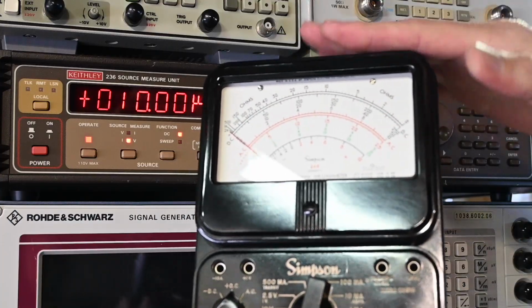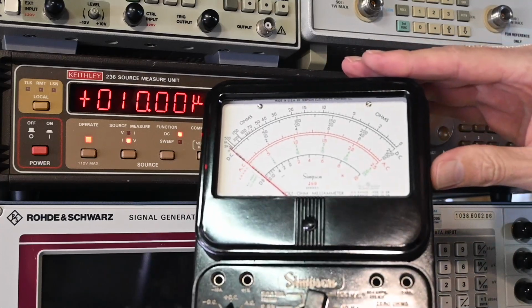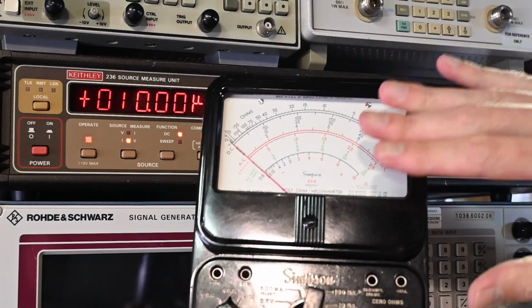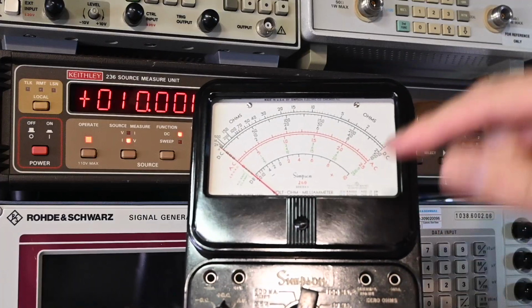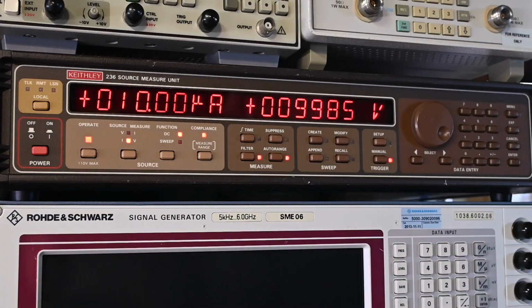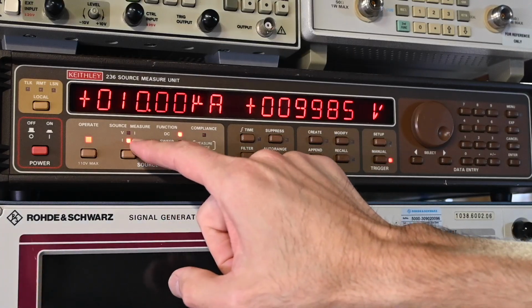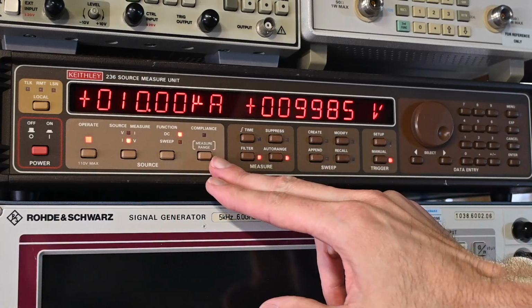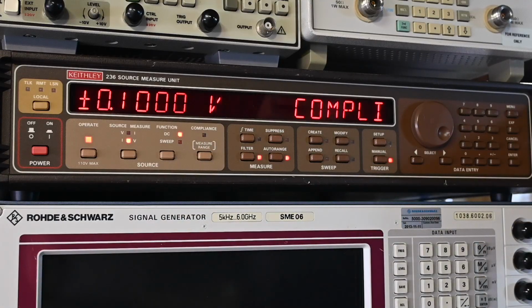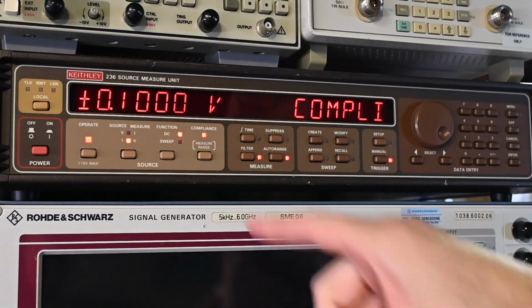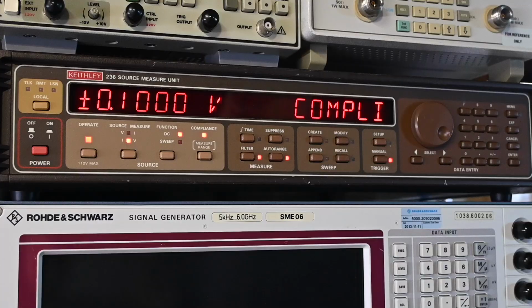Now again, with the microamp range that this has, and there's no protection, you have to be very careful. You would never want to hook a battery or something like that to power this meter. That would completely destroy the movement in the meter. You have to use a source like I'm using here with this Keithley 236, or a power supply that has a similar capability that can control down to the microamp range. Right now this is set to 10 microamps, so it's in constant current mode. You can see right now it's sourcing current, measuring voltage. It's also in the compliance mode, and that's really important because this can output up to 110 volts DC. In the compliance mode, it's set to a maximum output of just 100 millivolts right now.